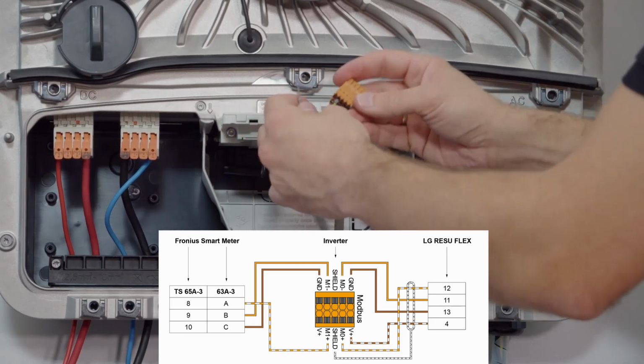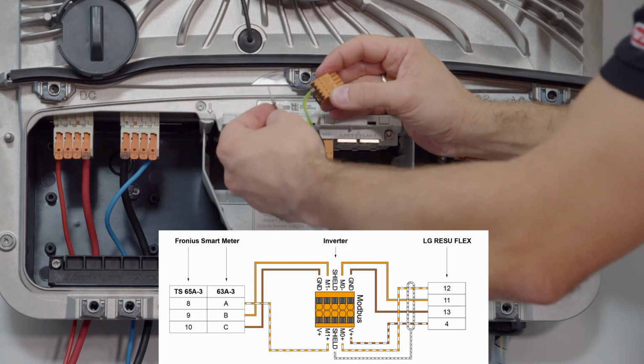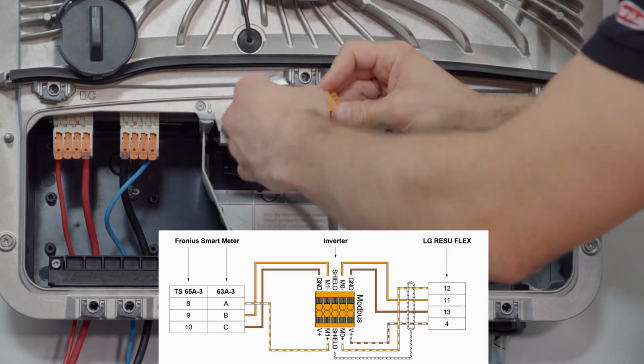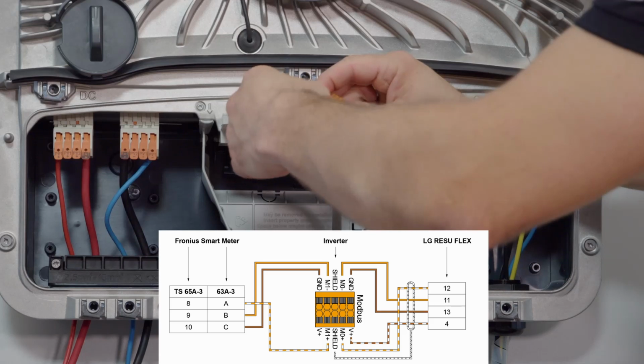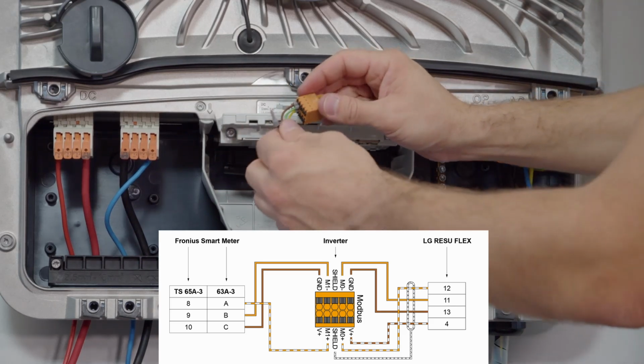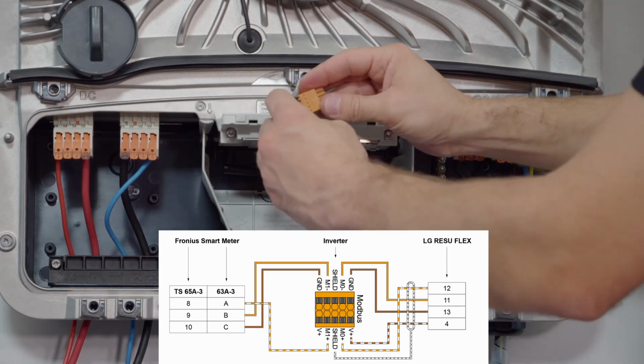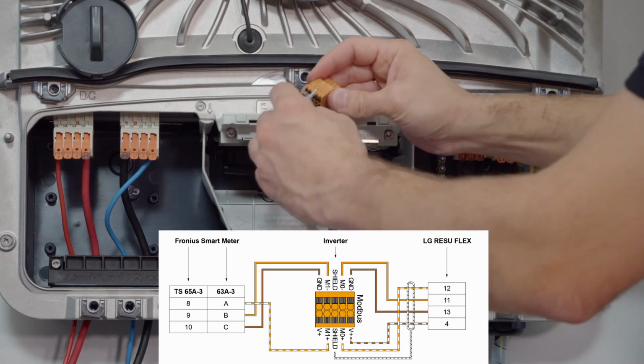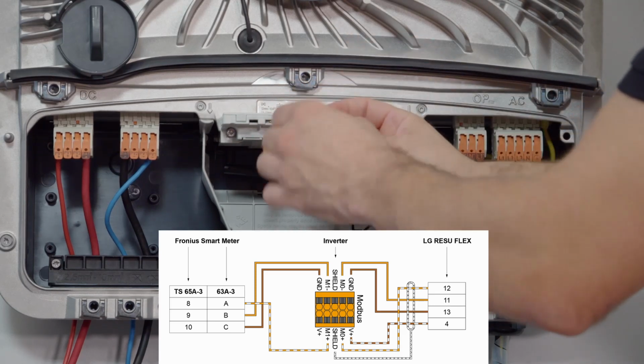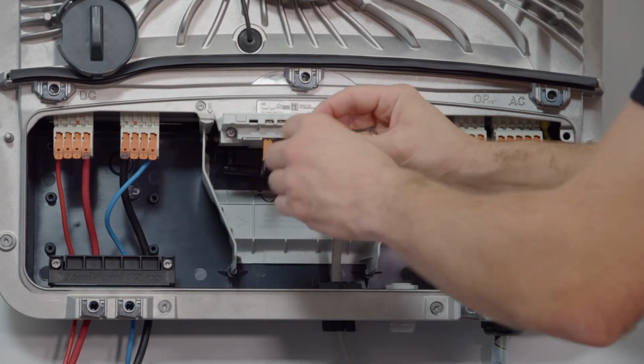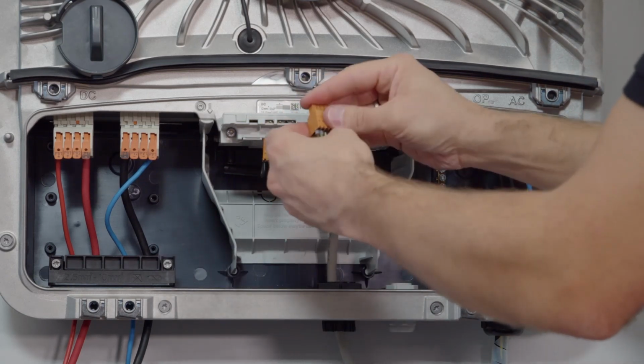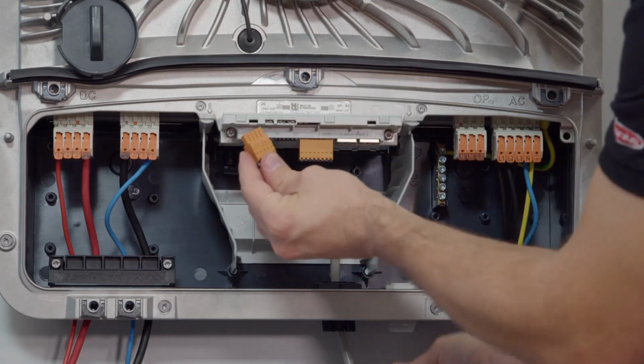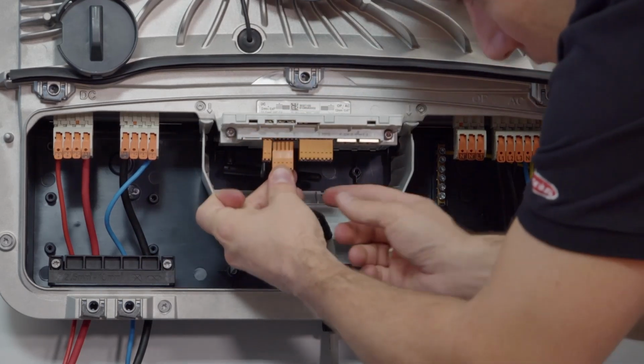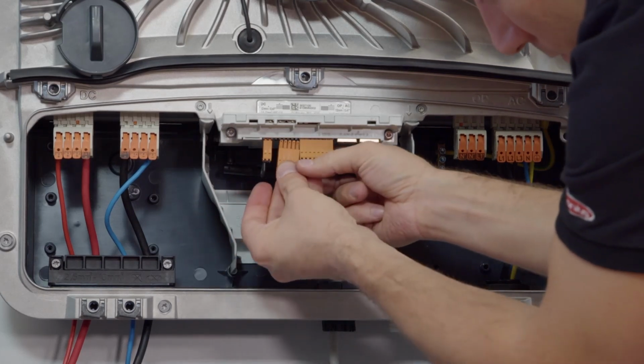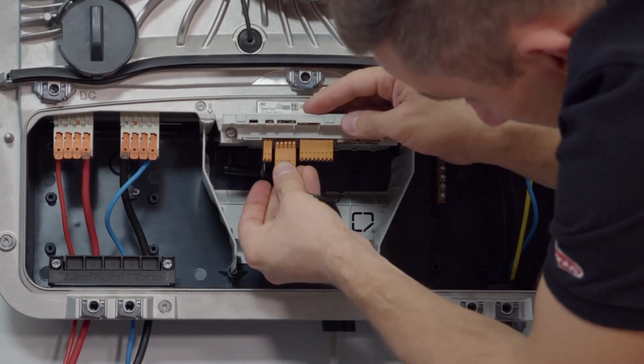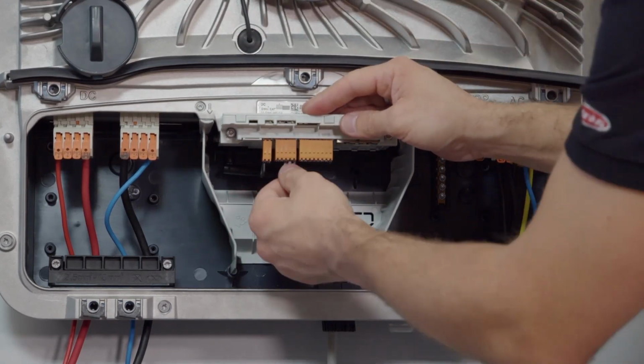And then for finishing, we have our ground contactor, and therefore we are using the ground cable for the third pin of the Modbus communication. Then for the shielding of the cable, we have here unmantled the shielding, and then we go to the contact shield. You can read it on the plug, and then we are going with the cable plug direct to the shielding of the cable. Yeah, when you have your cable connected, you can then directly plug it back in to the GEN24 Plus device, and therefore the Modbus communication to the GEN24 Plus is finished.